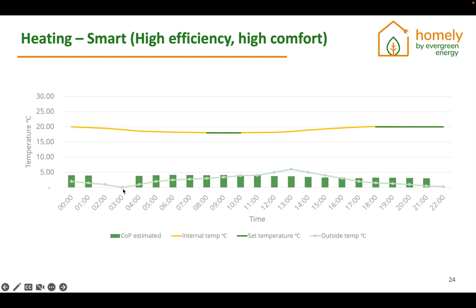Then as the temperature approaches zero, because the efficiency of the heat pump actually gets quite low, the heat pump is going to turn off. And then at 4 o'clock, it turns on again, but with very low flow temperatures, and slowly lands the internal temperature at the customer set point for the morning. The behavior here will depend on the house, since every house is going to be different, and it might actually be that the best scenario for this house is to just keep the house at 20 degrees with very, very low flow temperatures all the way throughout the day.